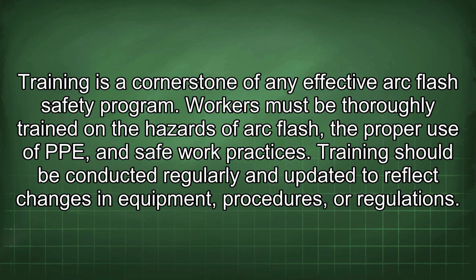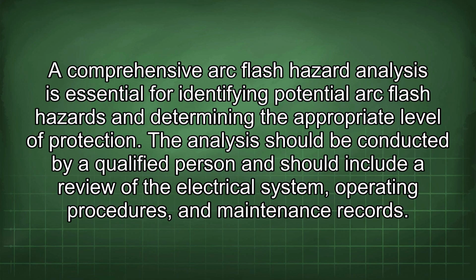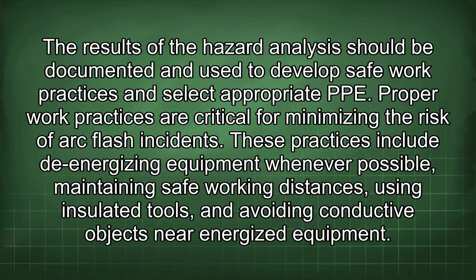Training is a cornerstone of any effective arc flash safety program. Workers must be thoroughly trained on the hazards of arc flash, the proper use of PPE, and safe work practices. Training should be conducted regularly and updated to reflect changes in equipment, procedures, or regulations. A comprehensive arc flash hazard analysis is essential for identifying potential arc flash hazards and determining the appropriate level of protection. The analysis should be conducted by a qualified person and should include a review of the electrical system, operating procedures, and maintenance records. The results of the hazard analysis should be documented and used to develop safe work practices and select appropriate PPE.